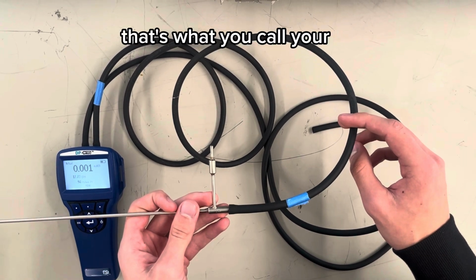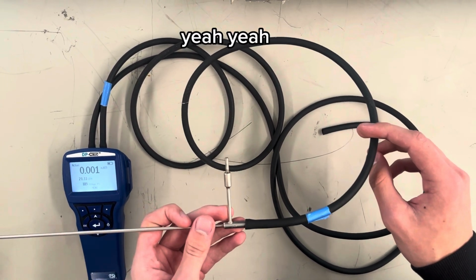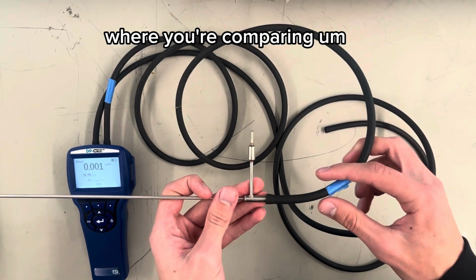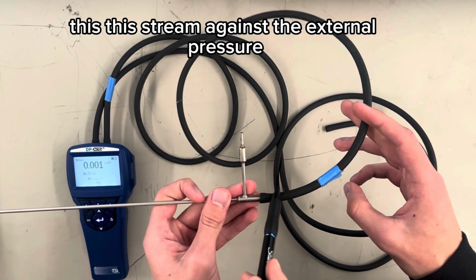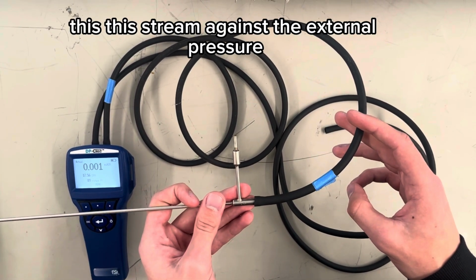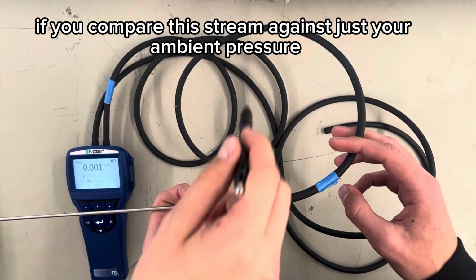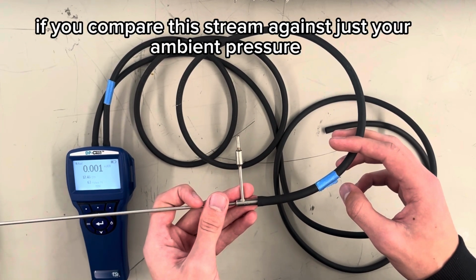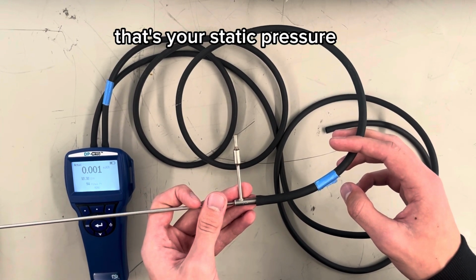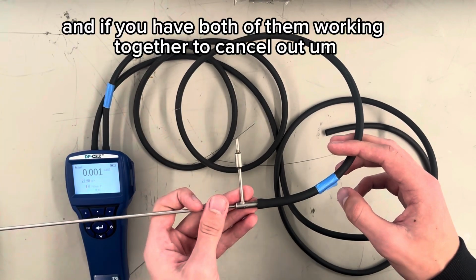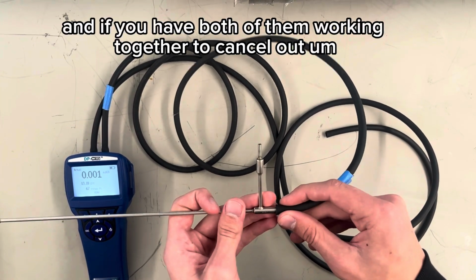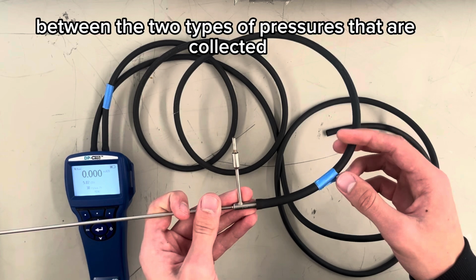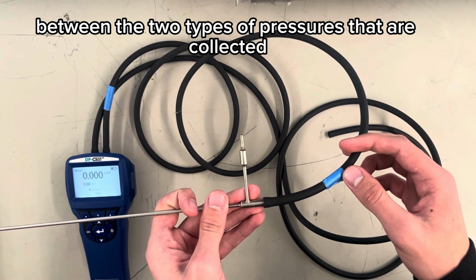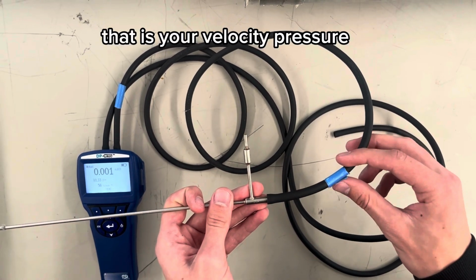Excuse me, that's your total pressure, where you're comparing this stream against the external pressure. If you compare against just your ambient pressure, that's your static pressure. And if you have both of them working together to cancel out, and find just the difference between the two types of pressures that are collected, that is your velocity pressure.